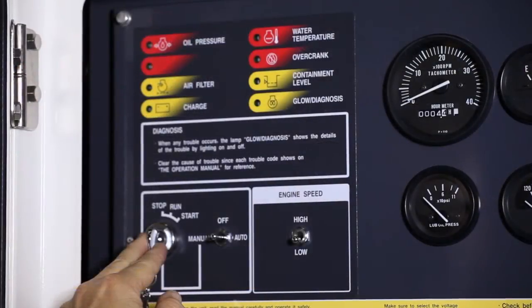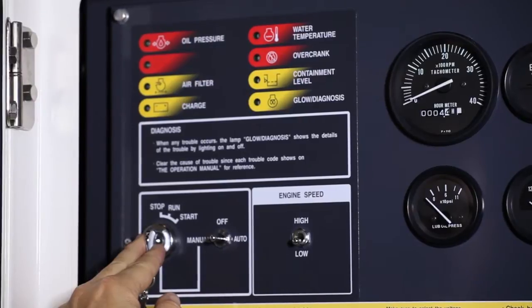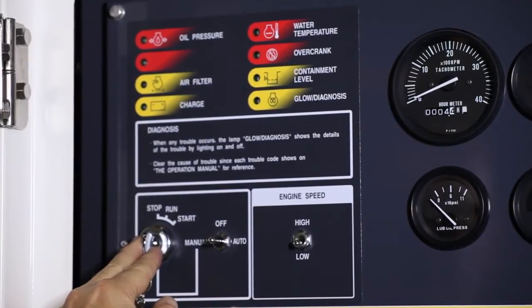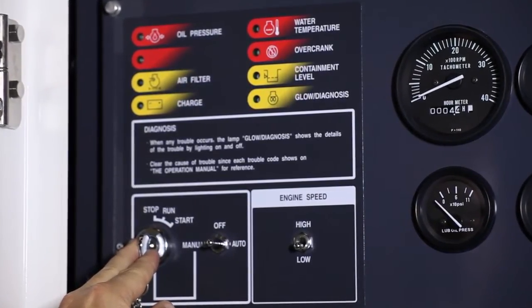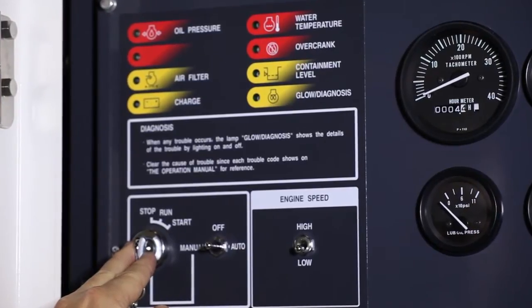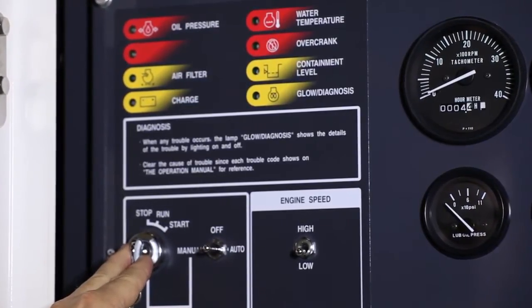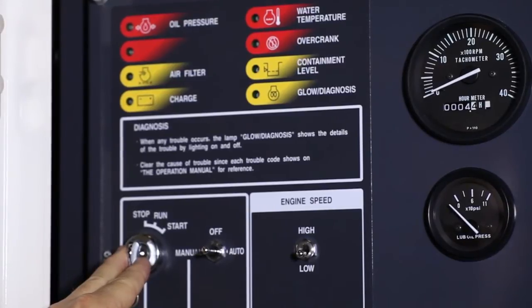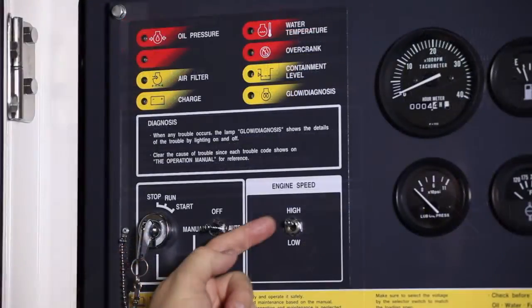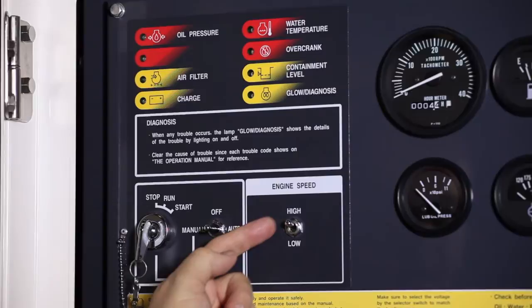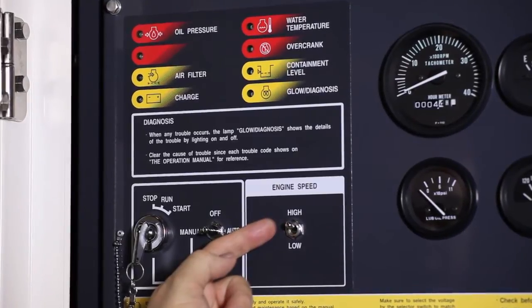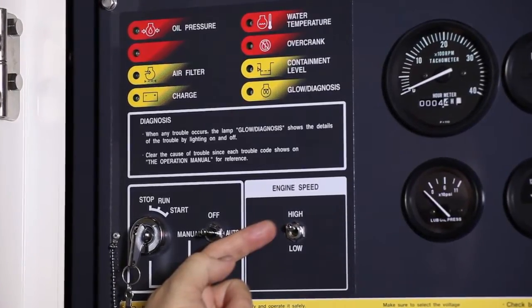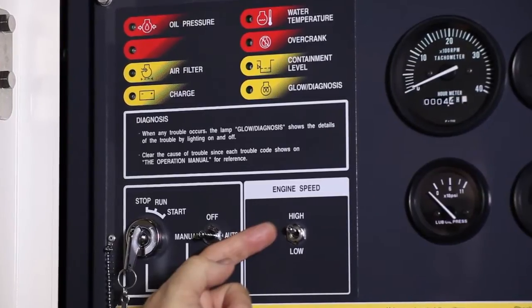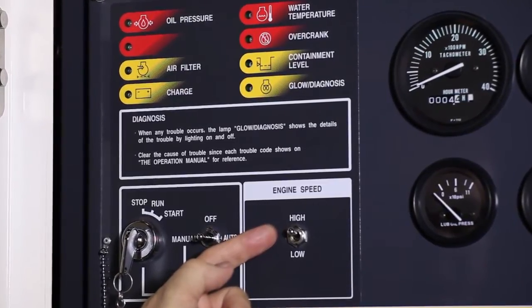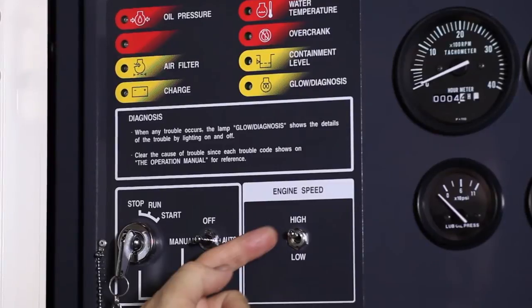The rotating start switch has two positions. Run will allow the generator to power up and turn on the self-priming pump if needed to reprime the engine. Turning the switch to start will start the generator set, and the switch will return to the run position once you let go. There is also an engine high-low speed switch. Useful for letting an engine warm up in cooler weather, this switch should be on low for a few minutes before moving to high. Please note, the generator power system will not allow you to energize power while the switch is in the low position.